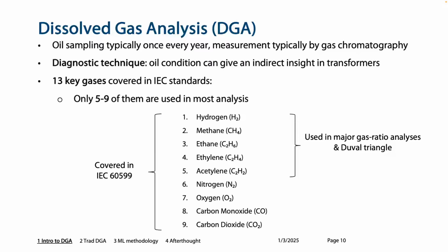It's not a necessary thing to do, and it's not sufficient evidence of any fault inside a transformer. Neither is the contrary true - if there are faults in a transformer, they may not reflect into the gas content. This is why it's a little difficult to apply DGA directly, because there are so many things that can happen that may not be captured easily.